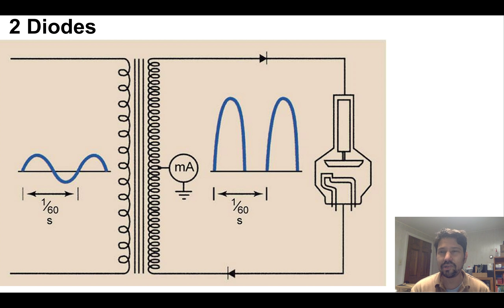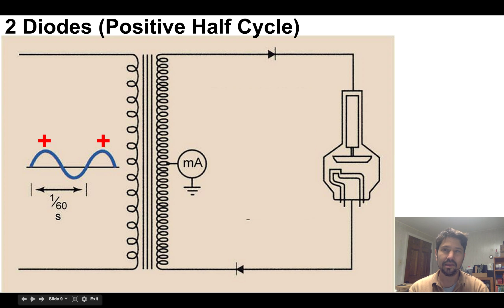So if we have a two diode system, and here's our high voltage transformer, so we're stepping it up. Let's see how we get from this input signal to this pulsating signal that hits the tube. So first, during the positive half of the cycle, when we're going up here and up here, not in this negative half, what happens?